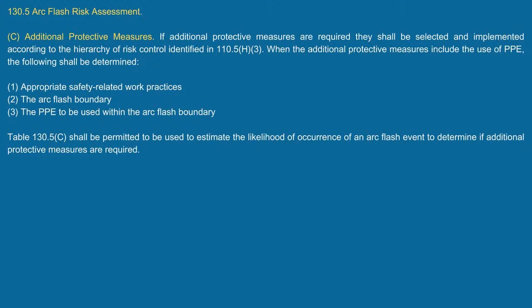Sure, and that's what I'm saying. All of that goes into it when you're doing your energized electrical work permit and writing those additional safety measures in. You always have to look and see what's there and what you need to do to protect yourself. Then the arc flash boundary, I will get into all that next week, and the PPE to be used. We'll start selecting all this next week. But what I'm trying to point out is this is the path we're following in order to make the assumptions for our selection, not only as it applies to the PPE and the arc flash boundary, but any additional safety measures that we need.